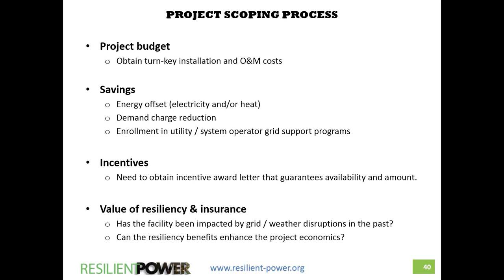Then there are the savings, which we talked about a little. I'd recommend the project developer take a hard look at the data available in a building: how much energy and power do they consume, on as granular a basis as possible. With Con Ed, we can get 15-minute utility bill data, so every 15 minutes we can see the building demand, and that's the level of detail we need for predicting the savings from an energy storage system.